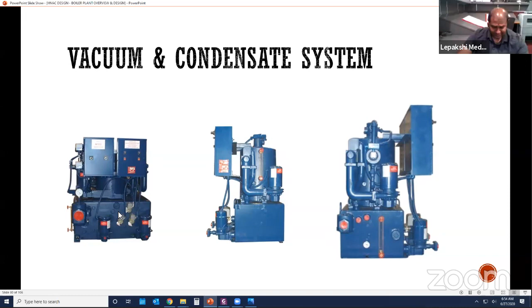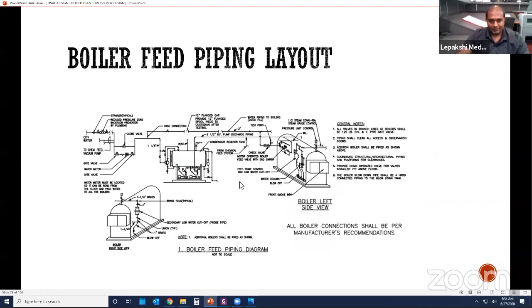Once the vacuum sucks that in, it comes over here. The bottom one is called the condensate receiver, and the top one is the vacuum. You can see 2 pumps on the vacuum and 2 on the condensate return. Once the condensate gets over here, from the condensate tank, it's going to be pumped back into the boiler feed. Over here, you see it says it's coming from VCP 1 and 2. VCP is vacuum and condensate pump. You have the condensate coming back into this boiler feed tank. Whatever amount you're losing, to compensate for that, you're filling it with fresh water. That's the scenario over here.